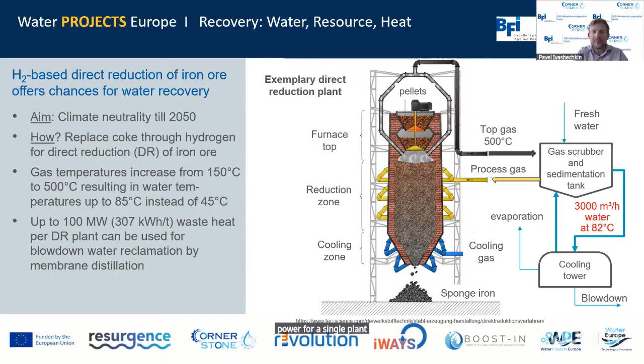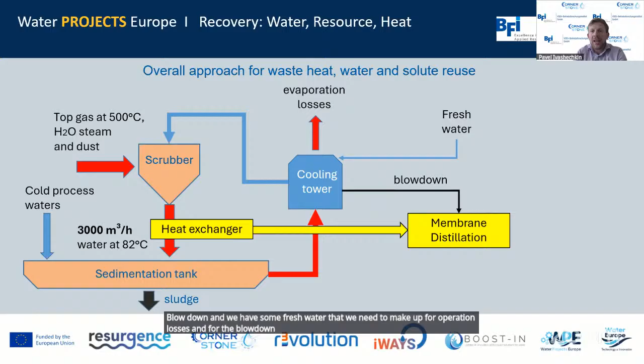The circuit is pretty simple: from the scrubber, the hot water goes to the sedimentation tank and then to the cooling tower. We have some blowdown, and we have some fresh water that we need to make up for the evaporation losses and for the blowdown.